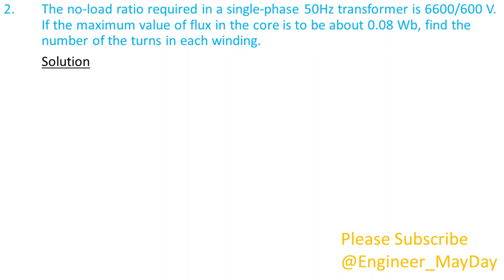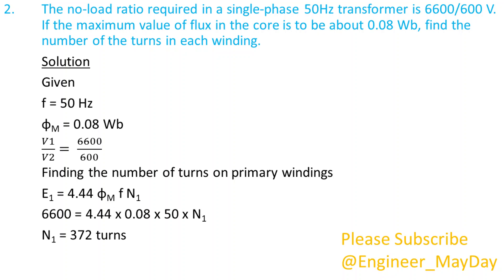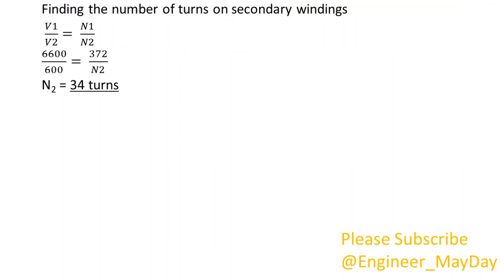Solution. Given: F equals 50 hertz. Maximum value of flux equals 0.08 weber. V1 over V2 equals 6,600 over 600. Finding the number of turns on primary winding: N1 equals 372 turns. Finding the number of turns on secondary winding: N2 equals 34 turns.